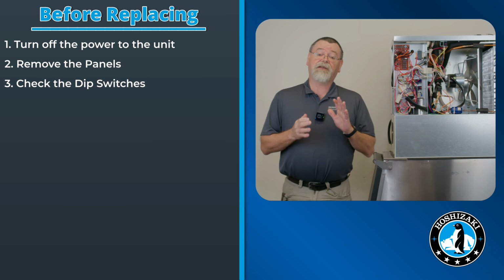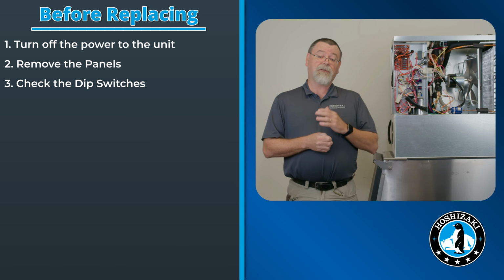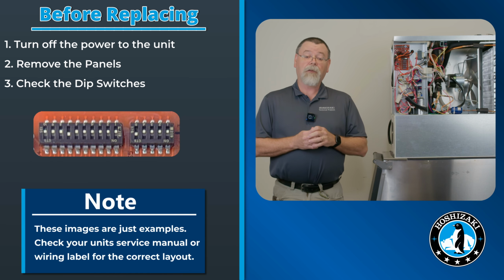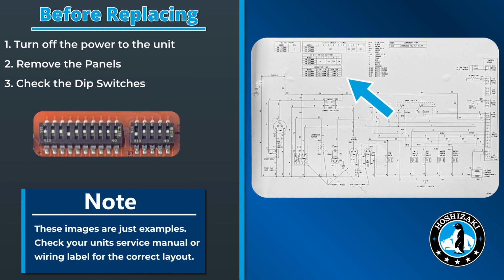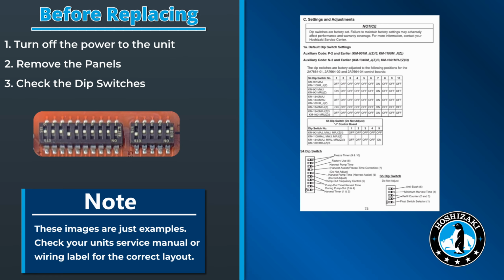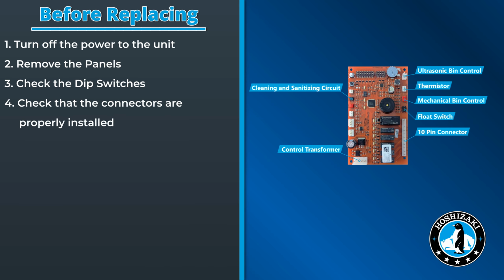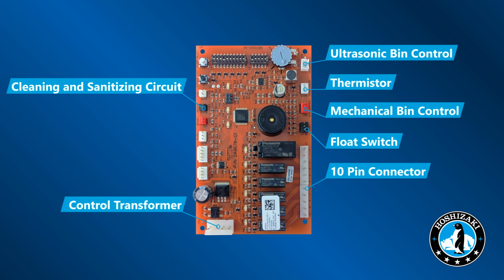Before we actually condemn a board, we need to make sure that the dip switches are set properly. We can do this by looking at the wiring label on the unit or looking in the service manual for the unit. Also, you want to make sure all the wires are connected to the right connections on the board. On the screen, it shows the layout of a K+ board, but check your unit service manual to make sure you have the correct layout for the unit that you have.